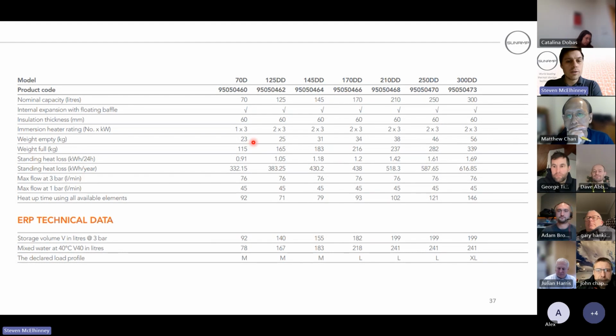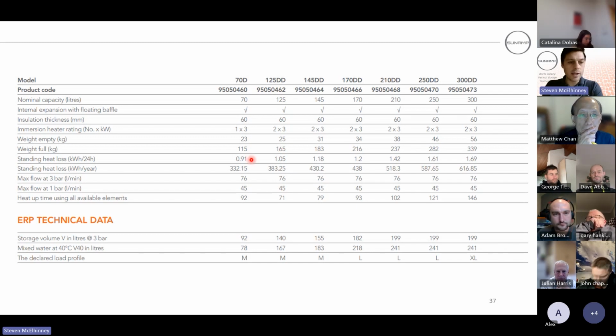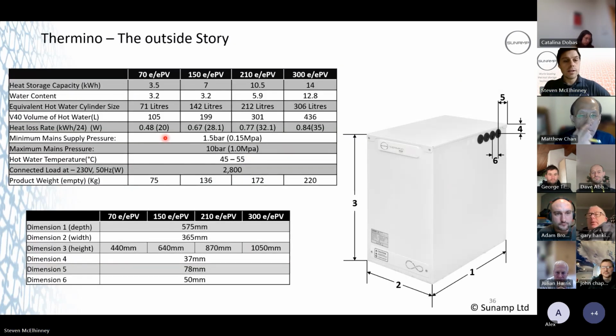Going on to this, this is a cylinder manufacturer. I don't want to mention their name, but they've got their models 70, 125, 145, 170 up to the 300. The important one here for me is the standing heat loss row. If you look at the 70, 0.91 kilowatt hours is what their cylinder would lose over a 24-hour period. So if you look at ours, we're almost half of what a cylinder's capable of doing.